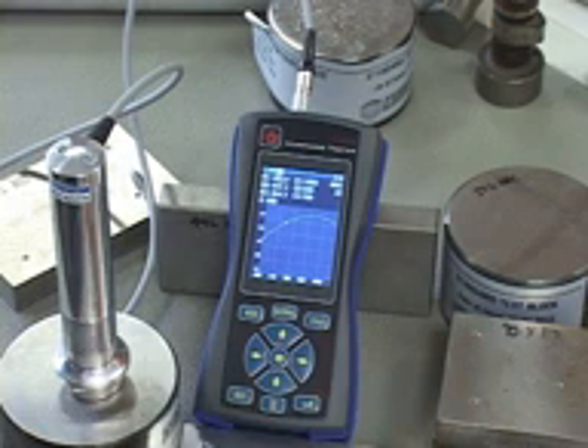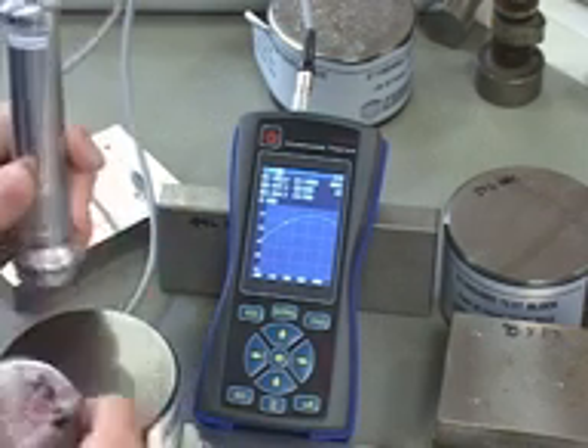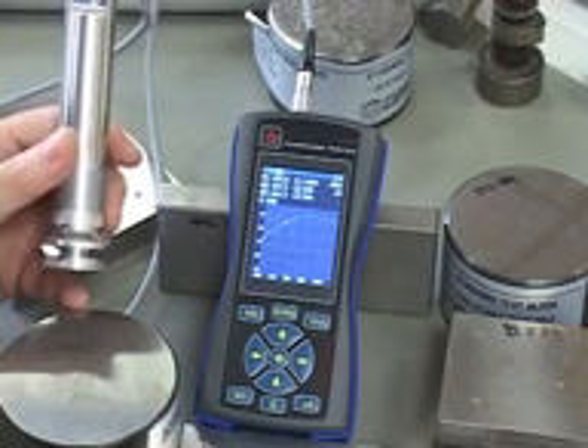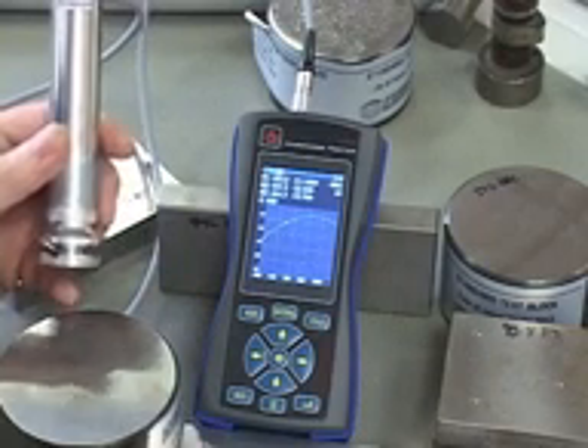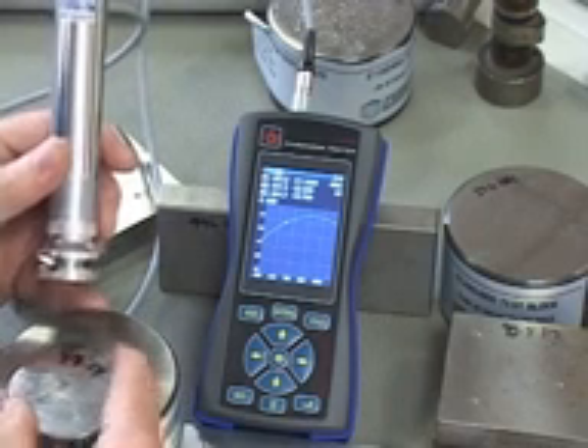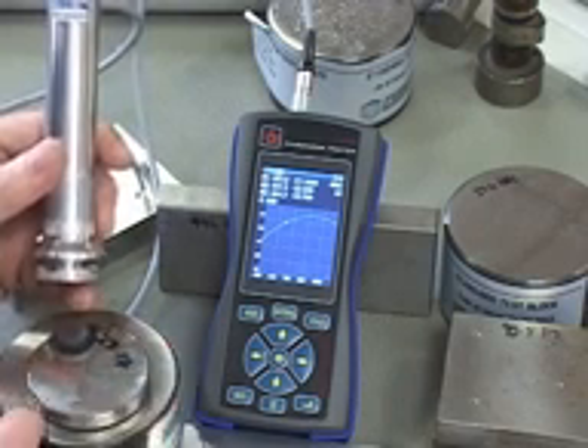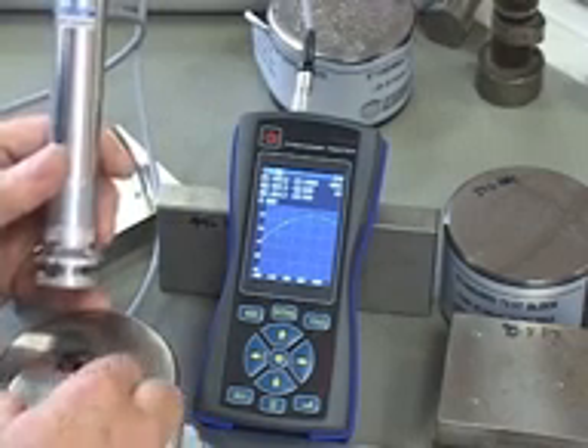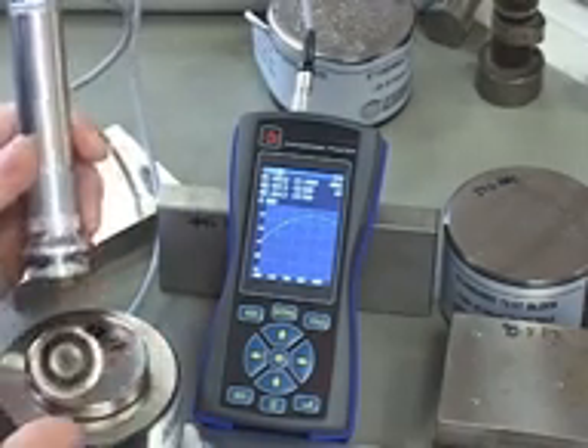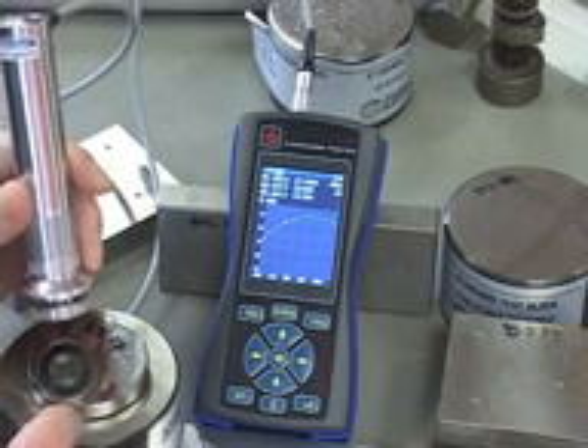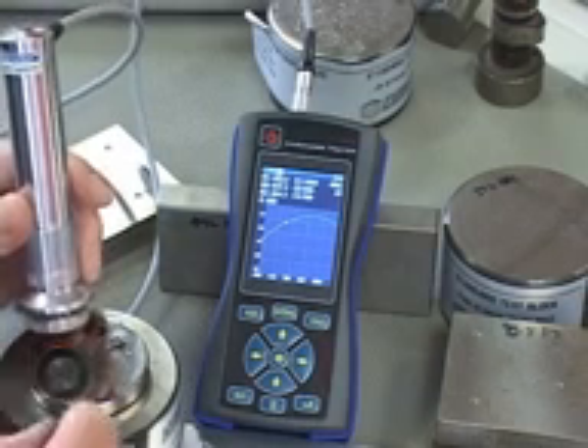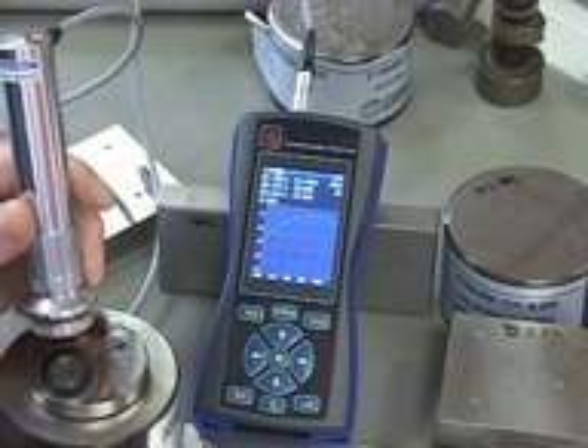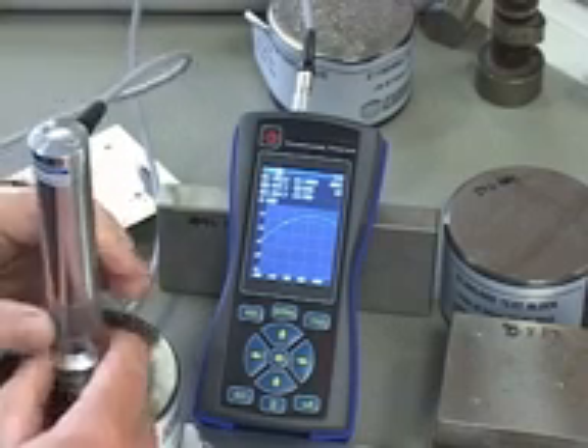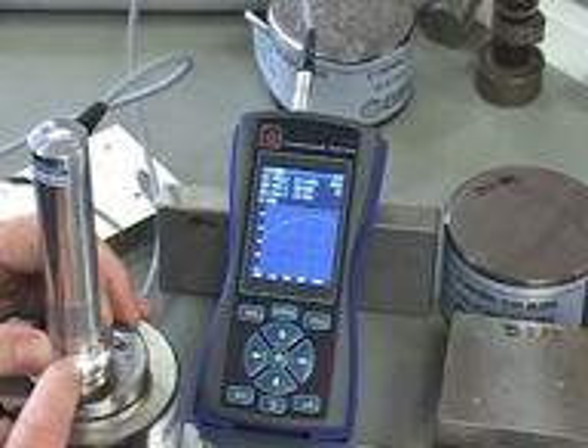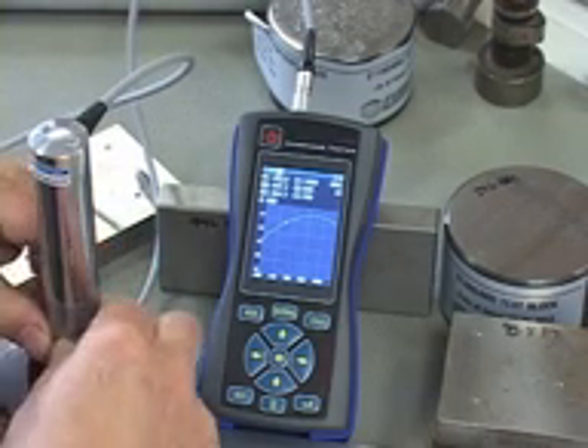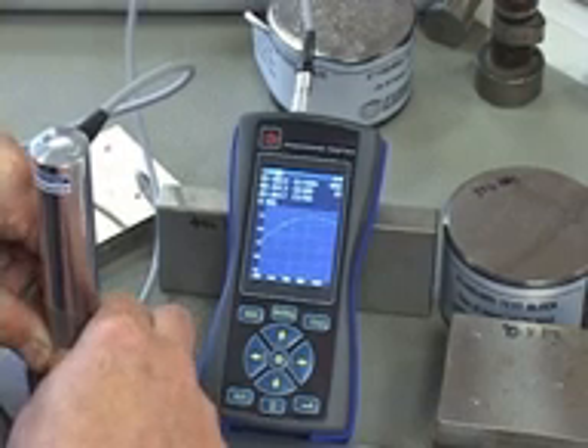So here, this is the 23.2. What I need to do is to use a heavier part. I can't just go onto my plastic table here or a wooden table. I need to ring it to something heavier to get the most accurate result, and what I have here is actually a lead calibration block. I flipped it upside down so I can ring the part to this, so now when I'm doing a test I'm getting the most accurate result rather than the vibration passing through the test block and potentially giving us an inaccurate result.